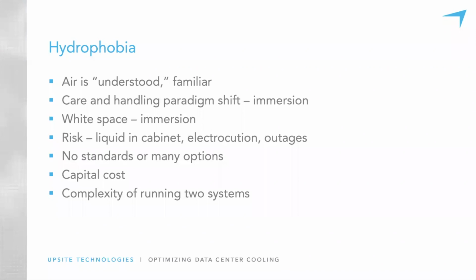Then there's the care and handling paradigm concern, and immersion cooling is probably the biggest one there. Putting all the equipment in a vat of liquid, and the issues that come around with having to maintain that equipment, is daunting for a number of people. Another one is the need to ask IT people to become plumbers. It's just not exactly something you want to be doing, asking IT people to be plumbers. But that, to some degree, needs to happen, or at least the awareness of the plumbing solutions that are occurring. White space, using up more space, is a concern, particularly with immersion. There's the risk of liquid in the cabinet. People are concerned about electrocution and outages, having water or liquid close to electricity. But these are things that can be mitigated with best practices.